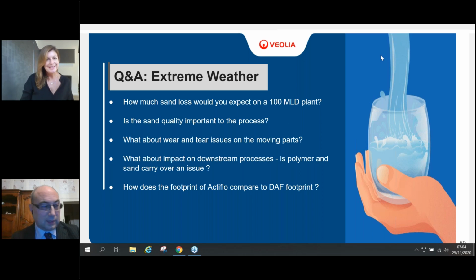That would be perfect. Let's make this our last question: what about the impact on the downstream processes? We're using polymer and sand, is there a carryover issue to the normal types of processes we might see downstream in a water treatment plant? Well, yes, there is. Of course, we use polymer, a flocculant, and this compound, if overdosed, is potentially fouling for sand filters and fouling for membranes, if you have any.